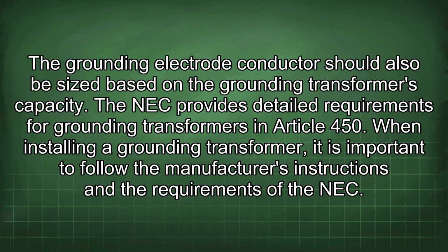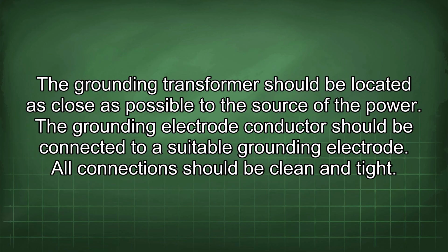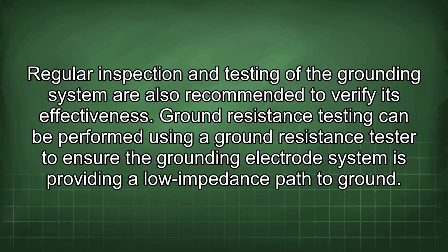The NEC provides detailed requirements for grounding transformers in Article 450. When installing a grounding transformer, it is important to follow the manufacturer's instructions and the requirements of the NEC. The grounding transformer should be located as close as possible to the source of the power. The grounding electrode conductor should be connected to a suitable grounding electrode. All connections should be clean and tight. Regular inspection and testing of the grounding system are also recommended to verify its effectiveness.